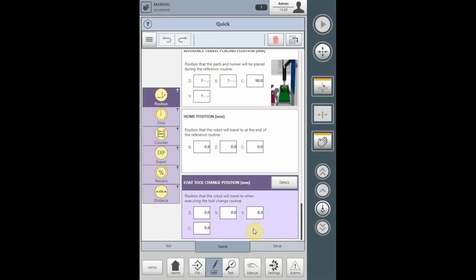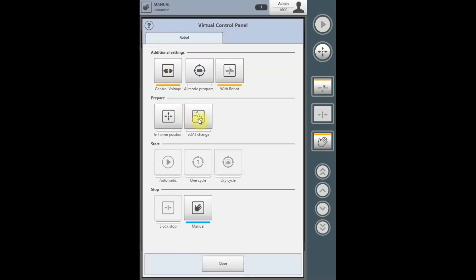The end of arm tool change position is a peripheral program that will allow you to drive the robot to a tool change position where a technician can work on the end of arm tool. The end of arm tool change position is only executed after the homing routine is completed. To activate it, select the mode of operation button and select end of arm tool change. The end of arm tool change will only execute after the robot executes the robot reference routine, arrives at the home position, and from that location it will drive to the end of arm tool change position.